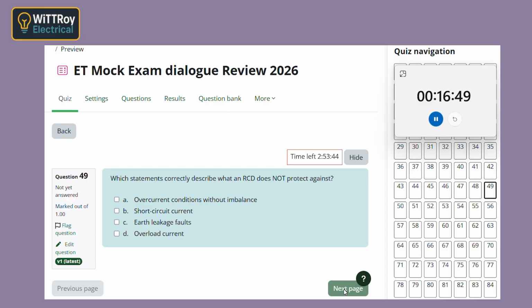Exactly right. That's the cause and effect. Too much current, but balanced current, means no residual imbalance, so the RCD may stay on while the cable overheats. That's why we still need fuses or circuit breakers. Yes, they deal with overcurrent. The RCD deals with imbalance. The option saying earth leakage faults is wrong because that is exactly what RCDs are intended to respond to.